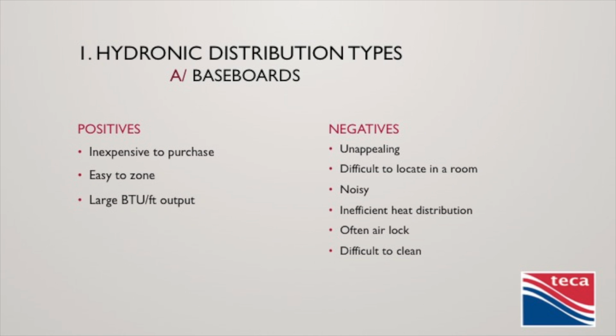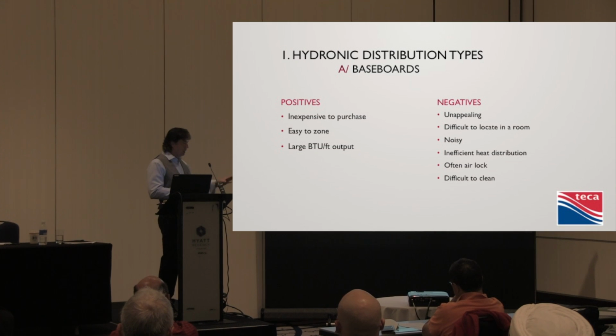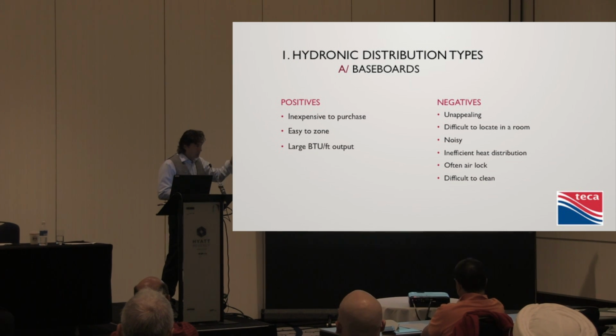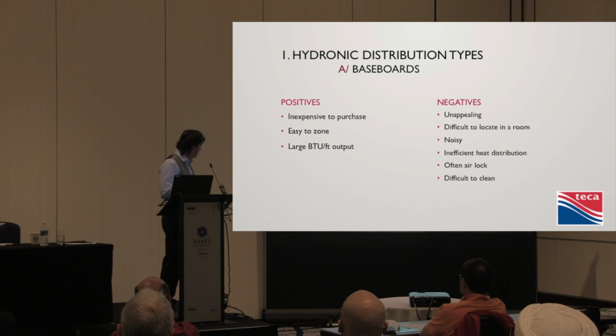So the positive of using baseboards is, it's inexpensive. To actually buy that baseboard we saw, per foot, is really not expensive. It's easy to zone. Well, you guys are like electric baseboard. You have a thermostat in a room that operates a baseboard. It's easy to zone. Large BTUs per foot. Well, it's got large BTUs per foot.